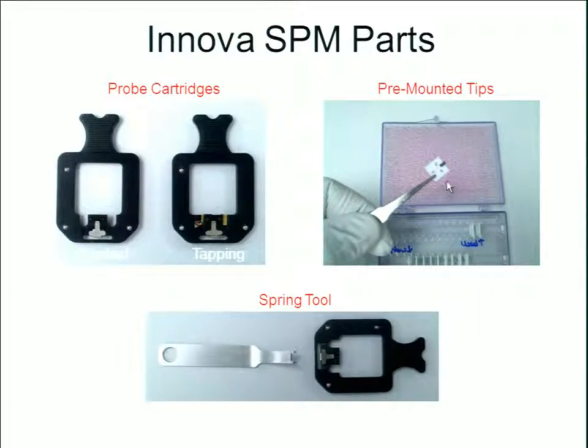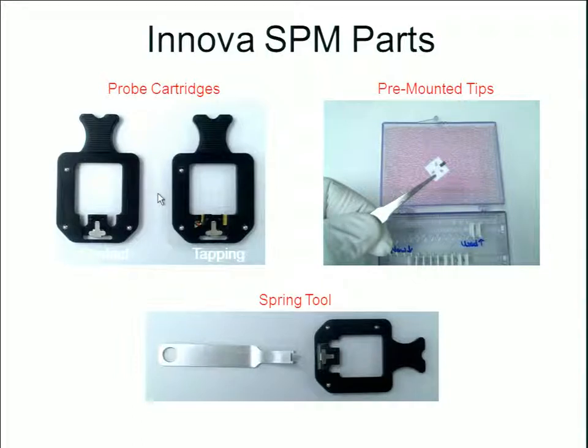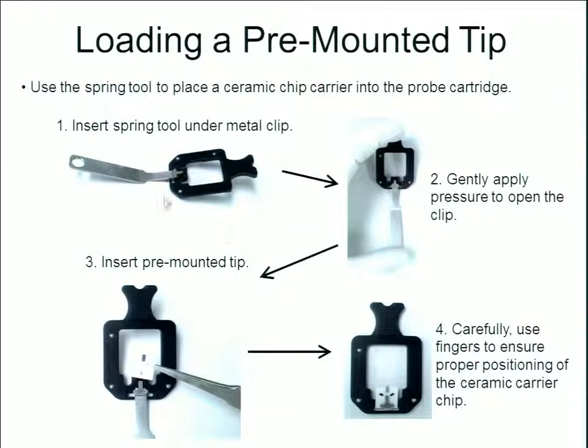That silicon chip is glued onto a ceramic piece called a chip carrier. The chip carrier has three small holes and basically snaps into place below a spring. You open this with a spring tool and snap in the chip carrier — which is glued to the chip containing your cantilever and probe. There are different types of probe cartridges: one for contact mode, and for tapping mode, one with a small piezoelectric and some electrical contacts.